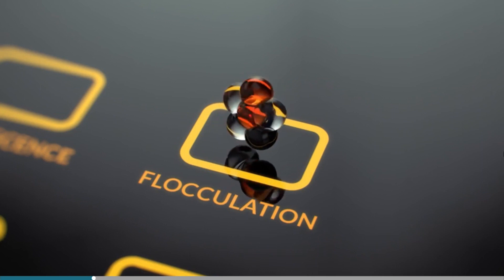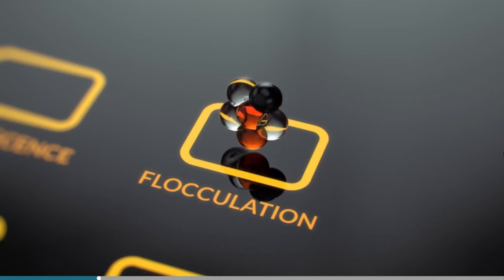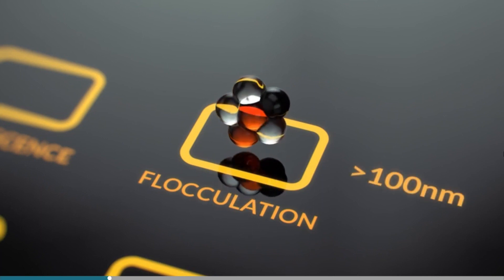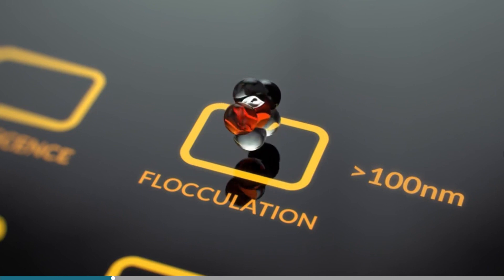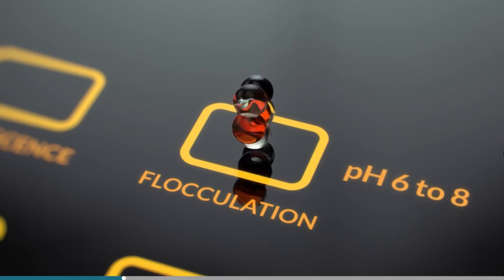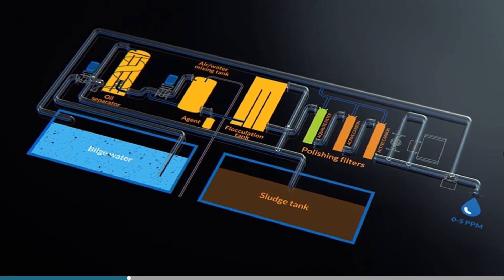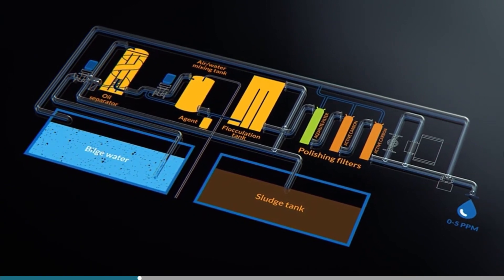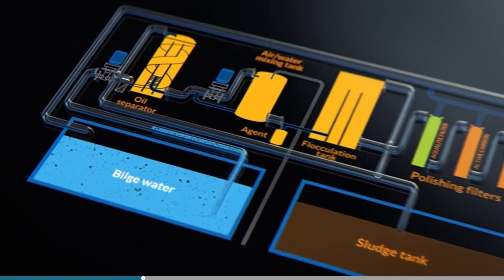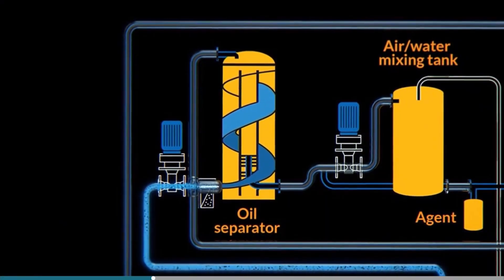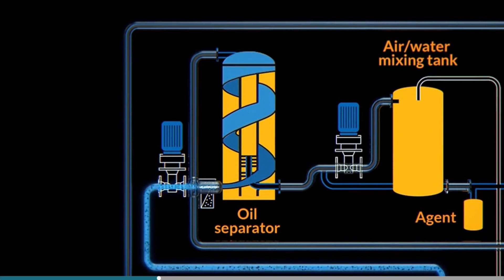Particles are then bound together through chemical action. This process will form particles larger than 100 nanometers, and these particles, called flocks, will then be able to settle. This works best at a pH of between 6 and 8. Bilge water from the bilge tank is fed to the first stage via a filter. In the oil separator, the bilge water circulates upwards around the periphery of the separator. The change of direction and drag helps to separate the oil from the water.